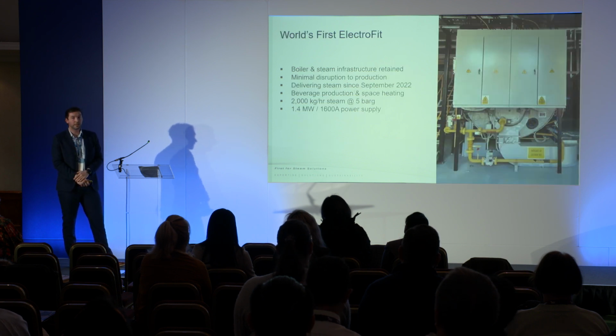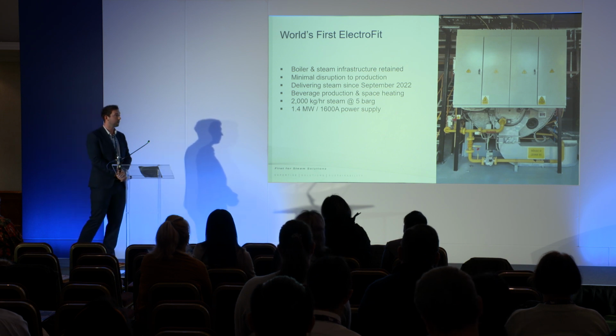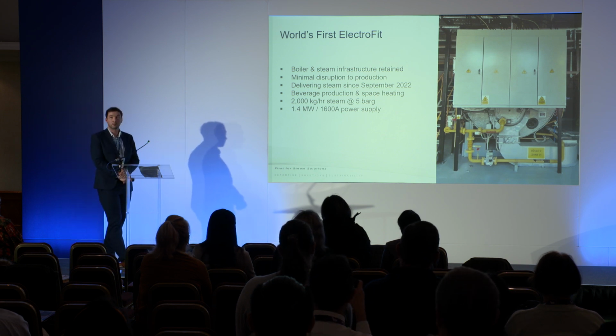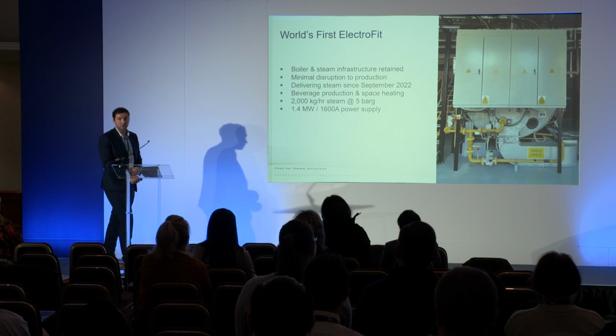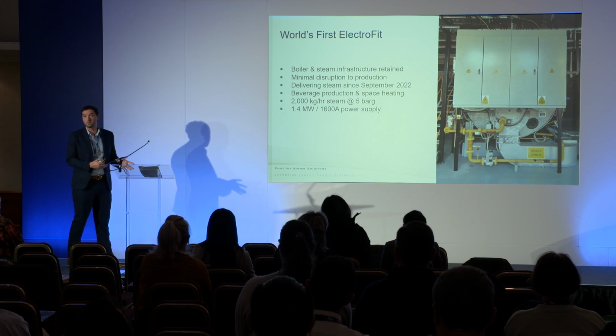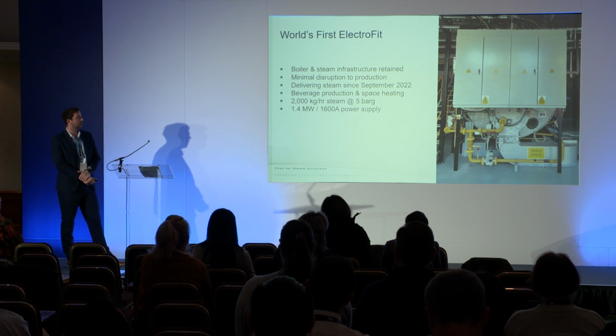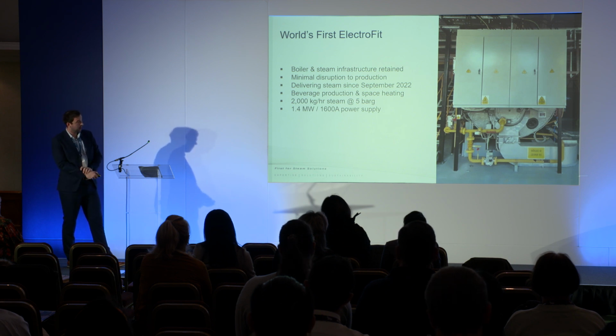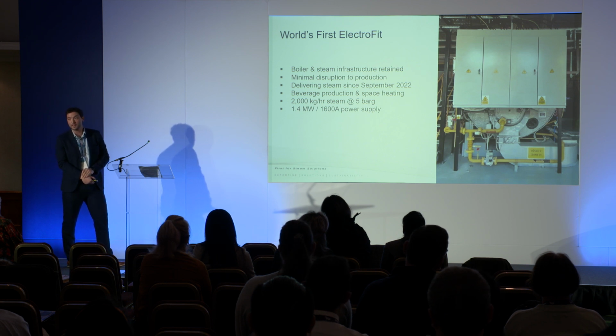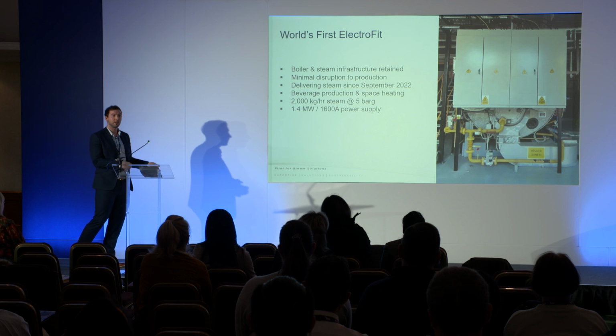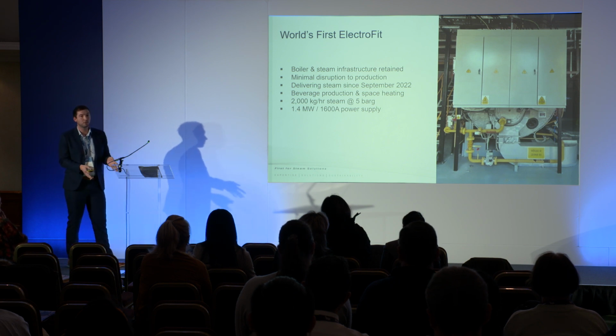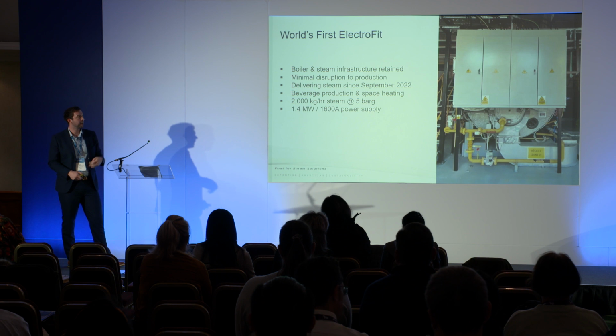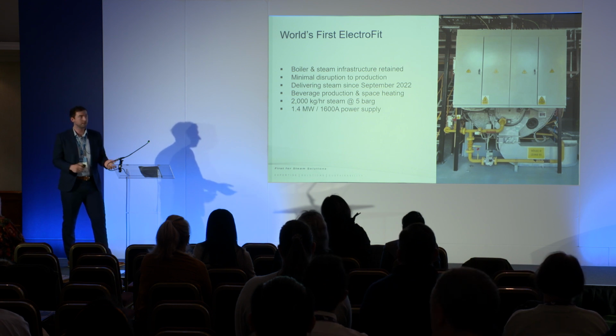And then over in Turkey, we've worked with one of our strategic accounts to actually electrify one of their boilers. So this was an existing gas boiler that we went along to, opened up, took the burner out, fitted electrical elements into the boiler, and completely converted that boiler to electricity. You can see the customer chose to leave the gas pipe in here. So if it didn't work or they want to switch back to gas, they can take this cabinet off, pull the elements out, put their burner back in. So there's no significant long-term modifications to this boiler, and that's how easy the switch is.